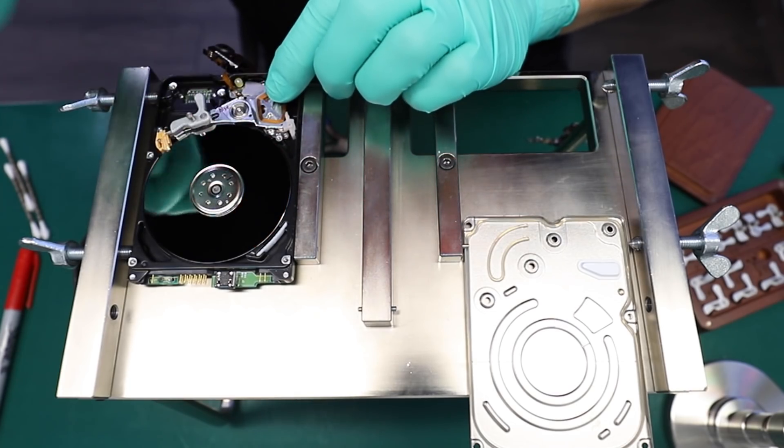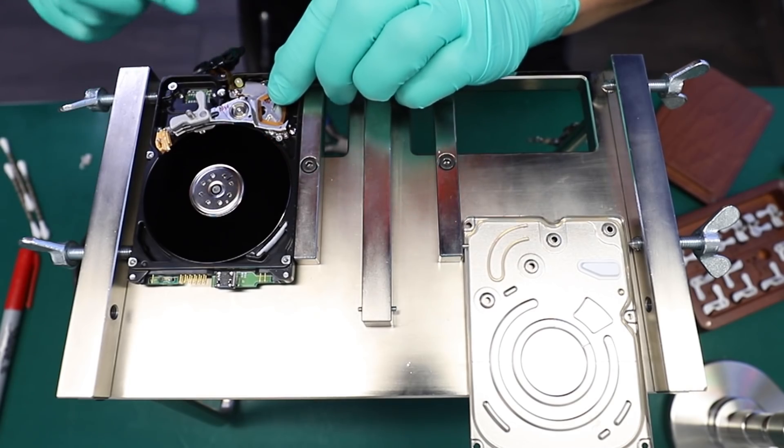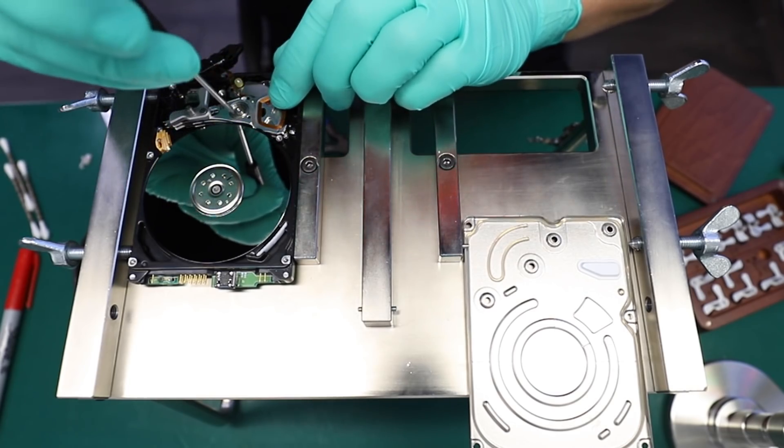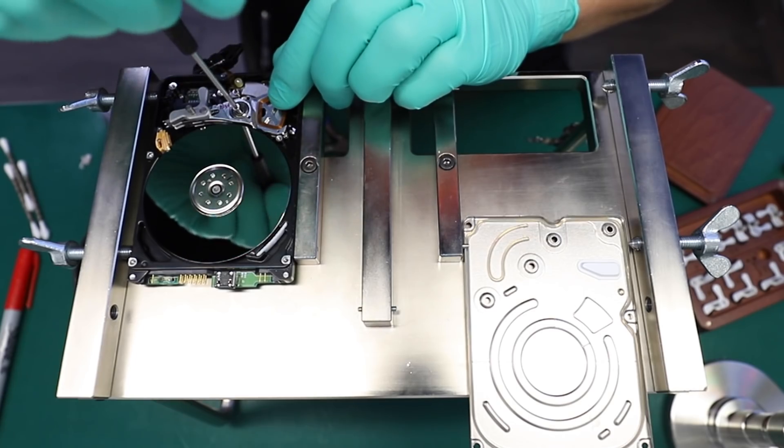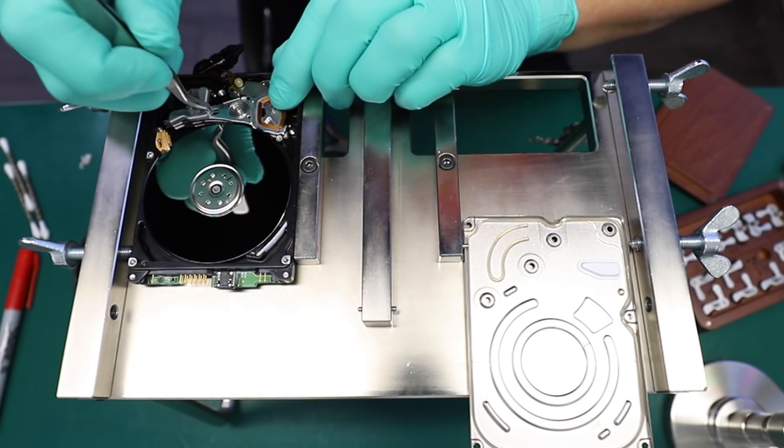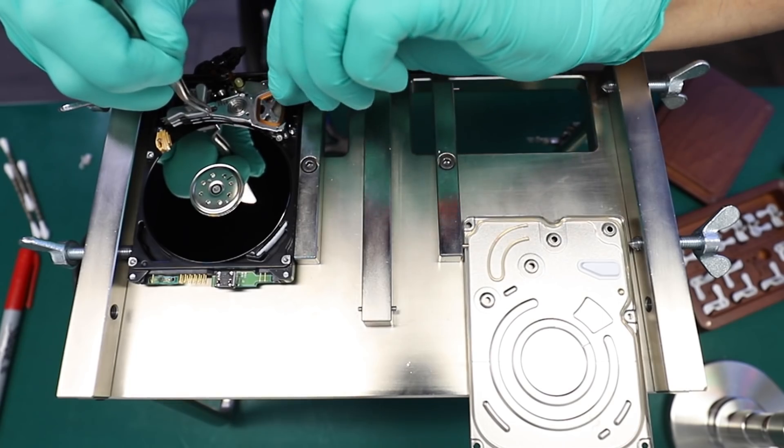When drives come in with seals that are open, they need full inspection. It's more work for us because when drives come in sealed, the causes of failure are natural and inspections can be done pretty precisely just by looking at the head assembly.